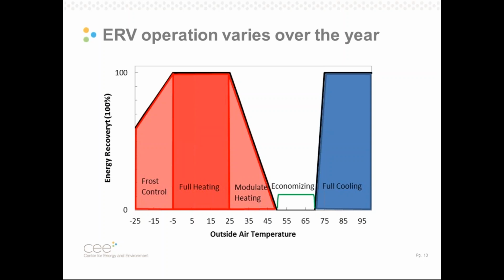I like to talk about energy recovery using this chart here. A couple manufacturers use this chart, and I really like it. It basically shows what an energy recovery system should be doing throughout the whole year in terms of outside air temperature on the horizontal axis, and on the vertical axis is the amount of energy recovery. So energy recovery systems should be on, they should be off, and then sometimes they can modulate in between.